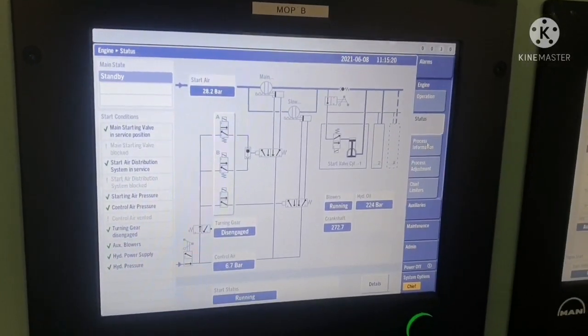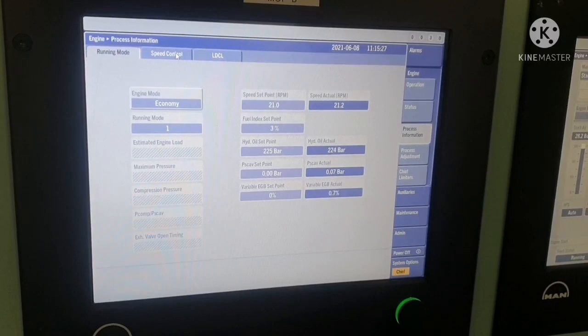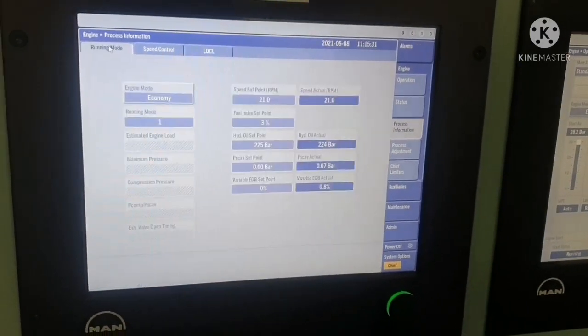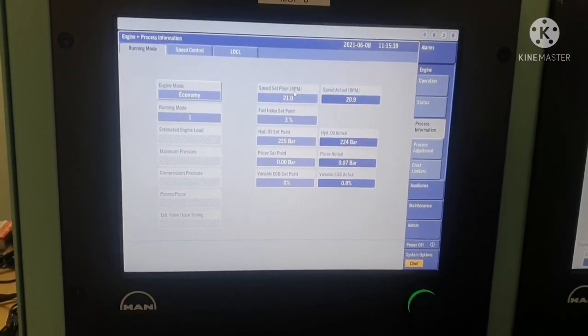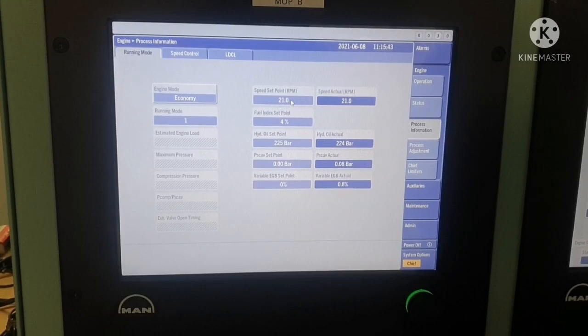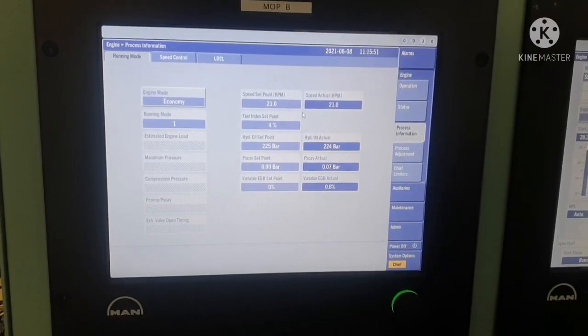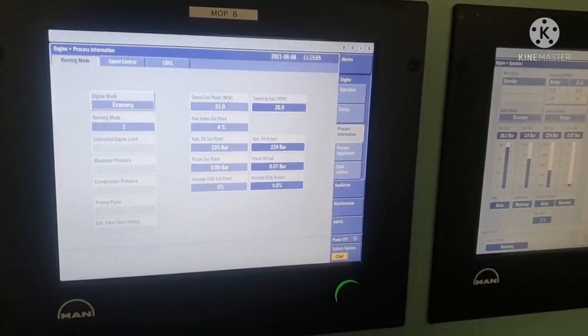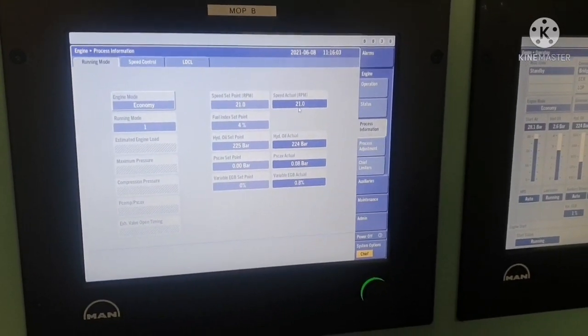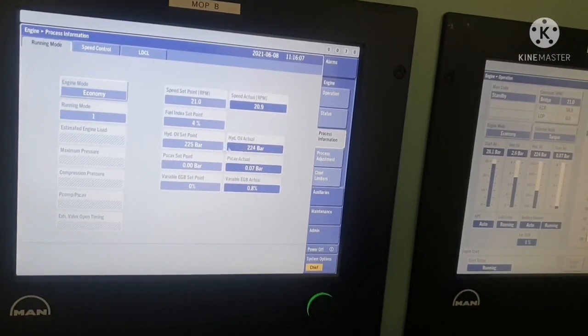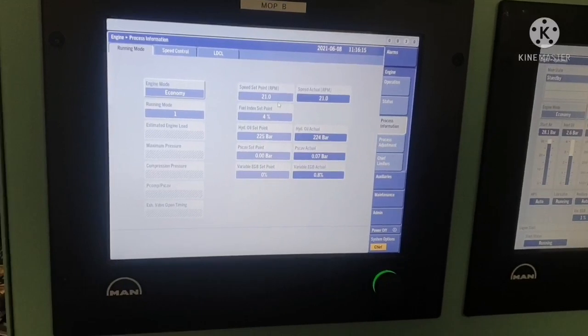Next is the process information section. There are three modes: running mode, speed control, and LDCL. In running mode you can see in which mode your engine is running — currently it is in economy mode. The RPM set point is 21 RPM and actual is also 21 RPM, so it is okay. Fuel index is 4%, hydraulic oil set pressure is 225 bar and actual is 224 bar. You can also see the variable EGB set point and scavenge point. You can adjust set points from this mode.